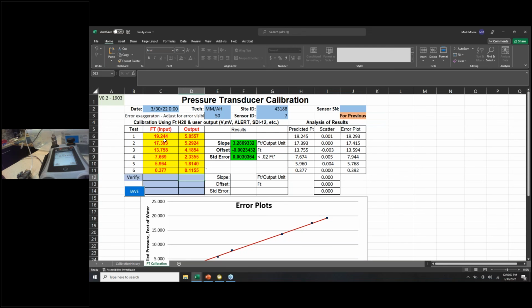So I'll give you guys a chance to look at this without me talking for just a moment. Think about, why was it not putting it out in feet? Shouldn't this be 19.24 is equal to 19.24? What was going on? Well, the answer was I changed the units of the PT. So the PT wasn't set to put it out in feet. The PT was set to put it out in some sort of other unit. And so because of that, it made it not a one-to-one relationship.